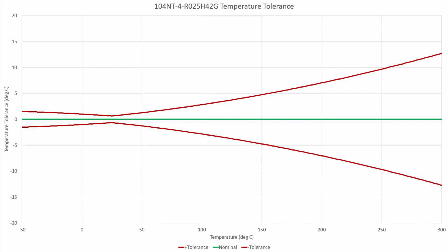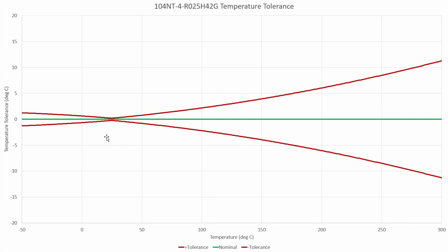I've made this chart dynamic, so we can investigate how changing the nominal resistance tolerance, the beta tolerance, and the rated temperature changes the temperature tolerance. Right now we're at 3% nominal resistance tolerance, 2% beta tolerance, and a rated temperature of 25 degrees Celsius. If we change that resistance tolerance from 3% to 1%, you'll notice at the rated temperature of 25 degrees Celsius, our temperature tolerance has decreased significantly. However, out at 200 or 300 degrees Celsius, we've only changed a little bit — from about plus or minus 13 degrees Celsius down to around 11.3.